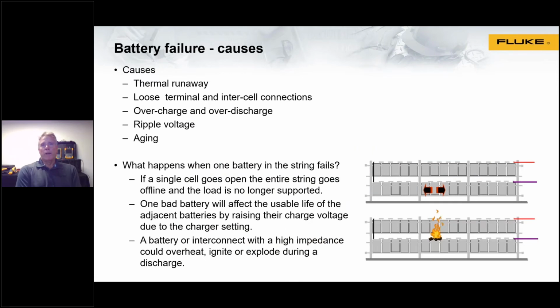So it's essential that people do what they can to make sure that, when these backup systems and batteries are called on, they are ready to work. One of the main causes of battery failure relates to heat. You can have conditions called thermal runaway, loose connections, loose intercell connections. It could be improper charging, both over and under charging over time. Also, what can cause battery failure is having excess ripple voltage on your charging system. So if you have a bad diode, for example, on your inverter, that could cause excess ripple voltage, which could impact battery health.